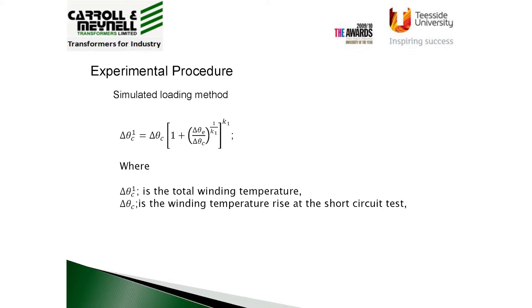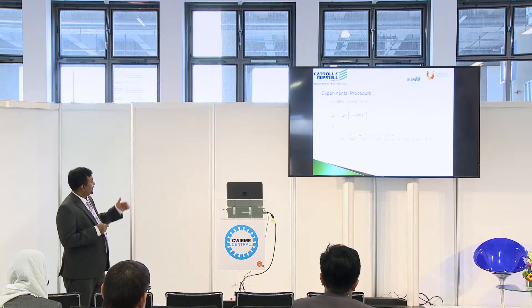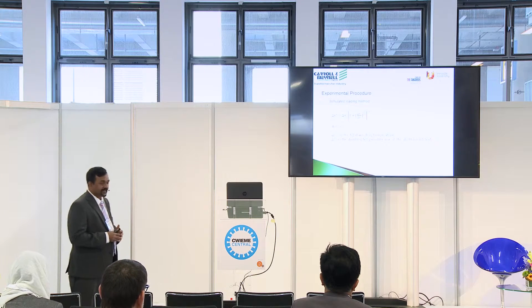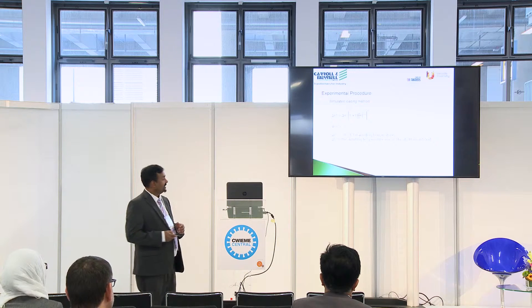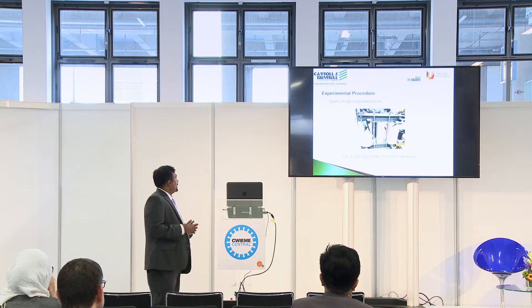This situation is addressed in transformer standard IEC 60076 section 11, where a simulated loading technique is defined. It is quite straightforward: in the first stage we load the core of the transformer with an open circuit secondary and record the temperature rise. Once the core is warm, we load the windings by short circuiting them — in which case we don't need megawatt-level power. Then an empirical formula defined by the standard estimates the overall temperature rise of the unit.